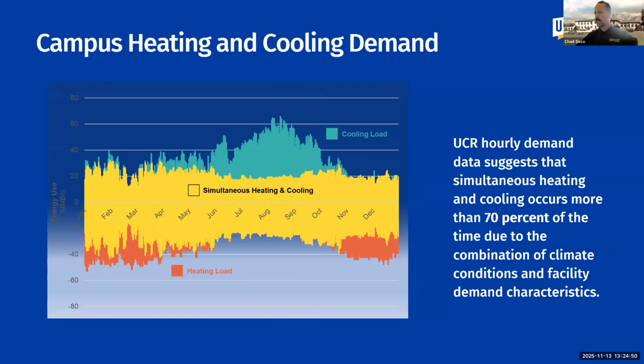So an assessment of our existing UCR hourly demand data during the decarb study found that simultaneous heating and cooling occurs more than 70% of the time, which we knew it occurred, but not at this rate. We didn't think 70%, which was great, right? It almost is similar to Stanford in that respect, where heat pumps will make a good energy impact in the campus.